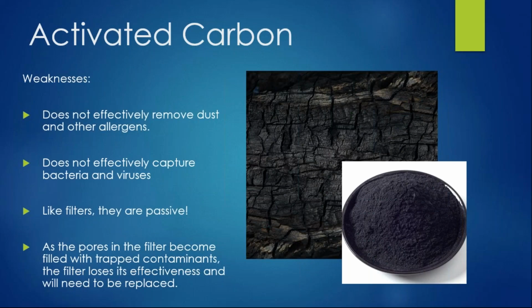So it can't do everything. It can't effectively remove dust and other allergens. It doesn't effectively capture bacteria and viruses. And like filters, they are passive, as I just mentioned. As the pores in the filter become more trapped with contaminant, the filter loses its effectiveness and will need to be replaced. So there's a life expectancy to carbon, whether it's in a filter or some other device. It will eventually have to be changed because it becomes loaded up.